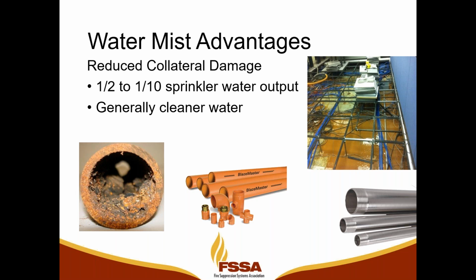When we compare a water mist system, especially in a light hazard situation where we're using a water mist nozzle that's got a glass bulb in it that's going to break under the heat of the fire and release the water, we're going to see about 50% of the water output that we would experience with a traditional sprinkler.